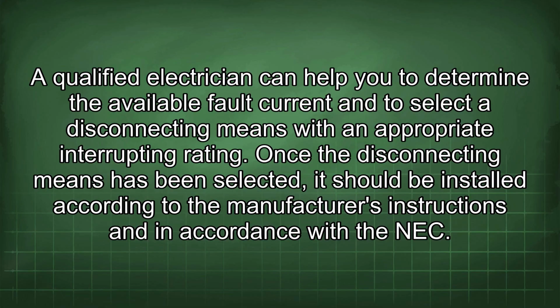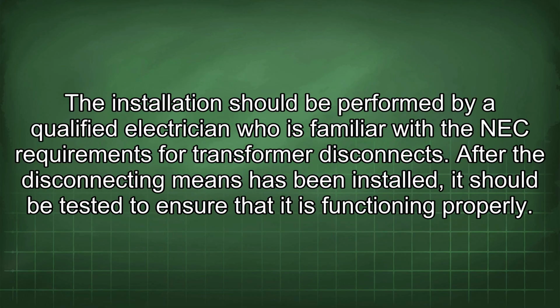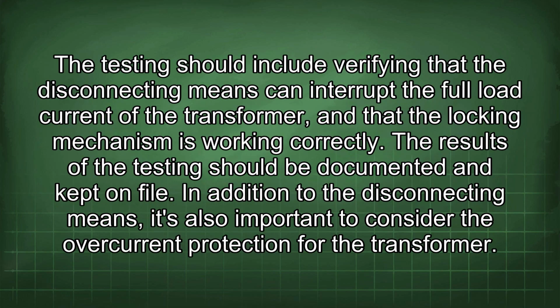Once the disconnecting means has been selected, it should be installed according to the manufacturer's instructions and in accordance with the NEC. The installation should be performed by a qualified electrician who is familiar with the NEC requirements for transformer disconnects. After the disconnecting means has been installed, it should be tested to ensure that it is functioning properly. The testing should include verifying that the disconnecting means can interrupt the full load current of the transformer and that the locking mechanism is working correctly. The results of the testing should be documented and kept on file.